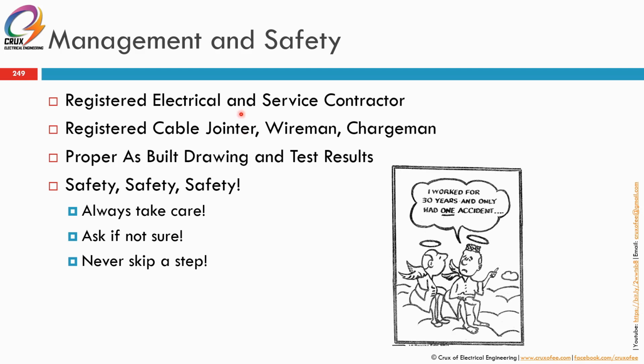So we have PK1 up to PK6, pencantum kabel 1, pencantum kabel 2. So same like jurutera electrical competent lah. So PK1 I think is for low voltage, PK2 is up to I think 11 kV or 33 kV, okay, and so on lah. Then wireman, we have a lot of wireman, the single phase wireman PW1, PW2, then 3-phase wireman PW3, PW4, then a special wireman for the neon lighting PW5, okay. And then we also have chargeman from A0 up to B4. So B4 you have B4 11 kV, B4 33 kV.